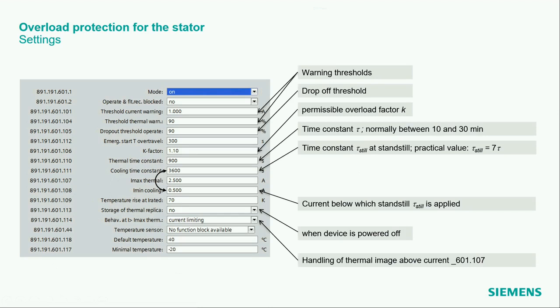As I mentioned before, this is a simplification of what happens in the motor. That means not all situations are described in a perfect way, and therefore I can have an overreaction of this model during the startup, or if there is a short circuit current. To overcome this, I can say the stress of the stator is described well when I have normal operating conditions. In case of a fault, this model can overreact.